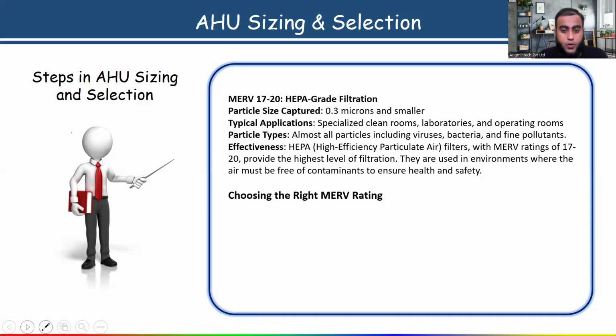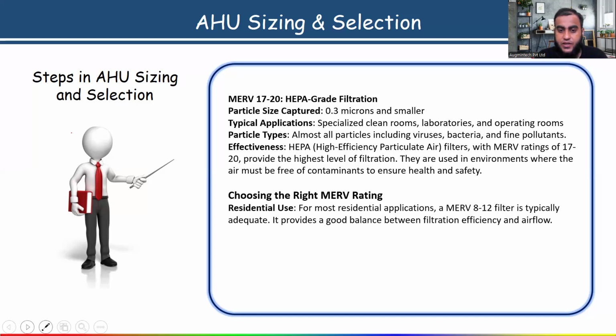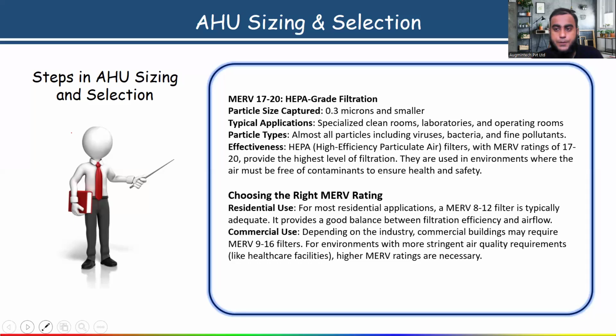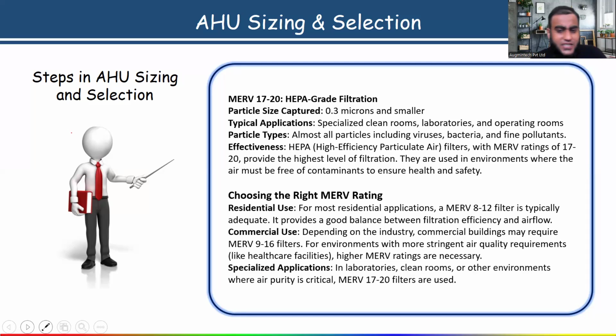Is it clear? Now, choosing the right MERV rating is given here. Which type of filter is best for which application? For most residential applications, a MERV 8 to 12 rating filter is typically adequate because it provides a good balance between filtration efficiency and airflow. And if you are doing the sizing and selection of an AHU for commercial use, depending on the industry, a commercial building may require MERV 9 to 16 rating filters. And for specialized applications like clean rooms or other environments where air purity is critical, we are using HEPA grade filtration, meaning MERV 17 to 20 rating filters are used.